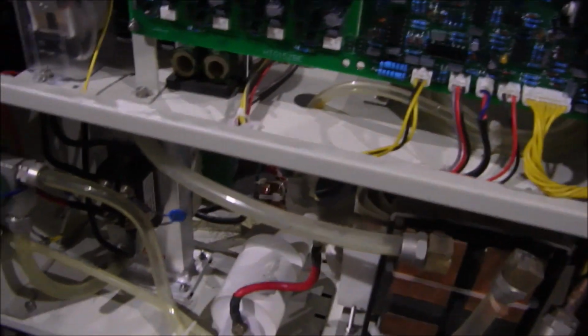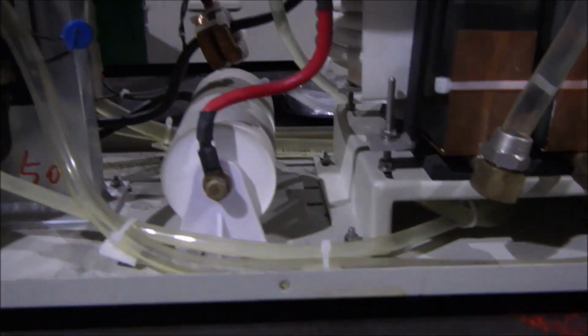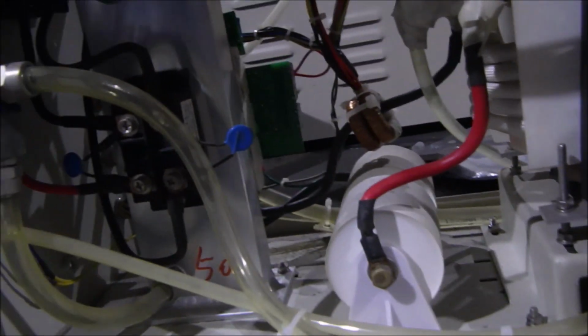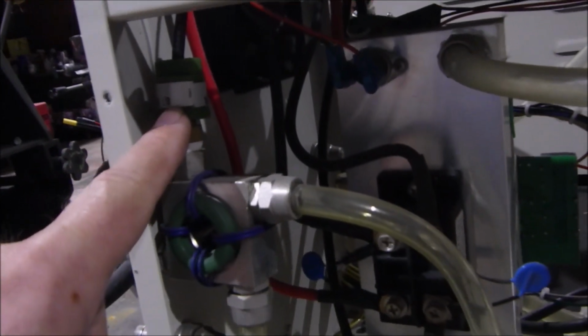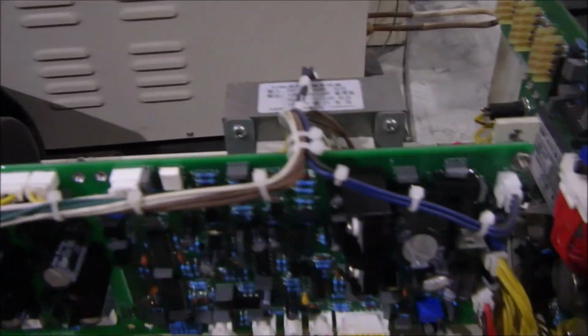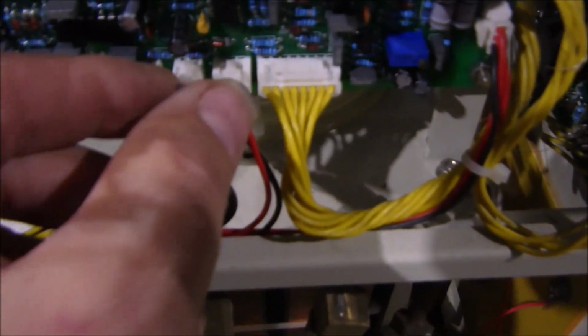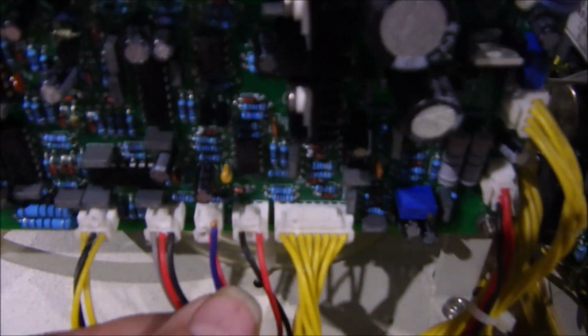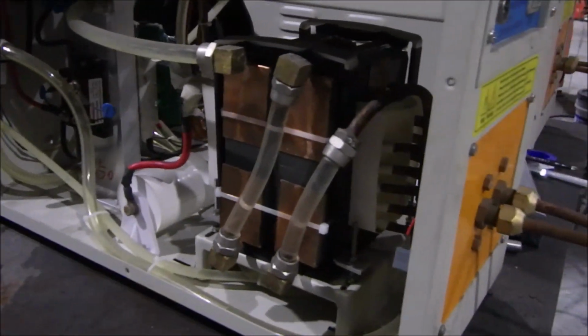So what else do you need to know about these things? There's a pressure sensor in them - trying to see where it is - ah, here it is, right here. This pressure sensor wants so many psi or so much water pressure to turn on, but really all it wants is flow. So on more than one of these, we've disconnected it, and if you just open the circuit it thinks it has pressure. That might void the warranty, I don't know, but these things don't really care about pressure at all - they just care about water flow.